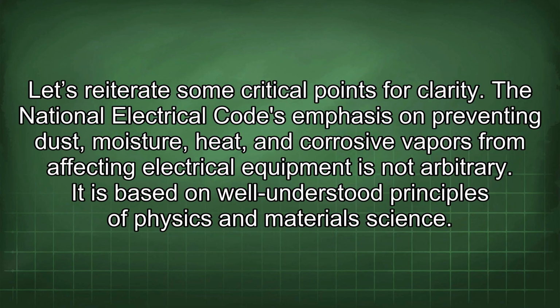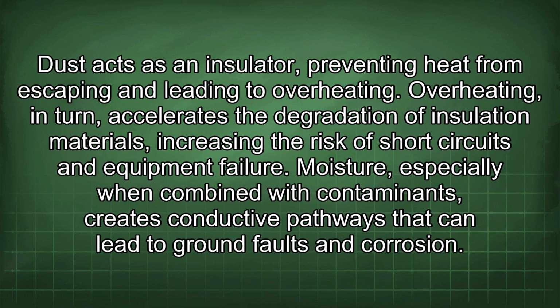Let's reiterate some critical points for clarity. The National Electrical Code's emphasis on preventing dust, moisture, heat, and corrosive vapors from affecting electrical equipment is not arbitrary. It is based on well-understood principles of physics and materials science. Dust acts as an insulator, preventing heat from escaping and leading to overheating. Overheating, in turn, accelerates the degradation of insulation materials, increasing the risk of short circuits and equipment failure.